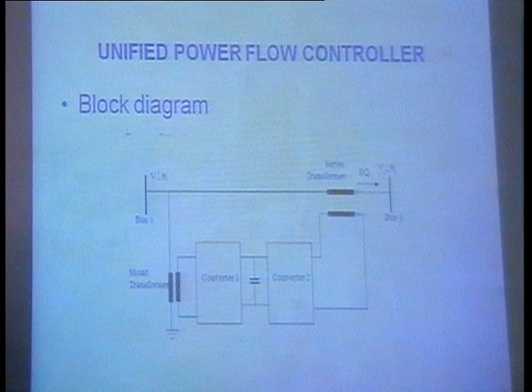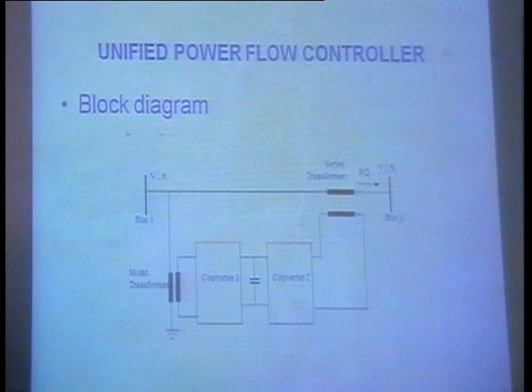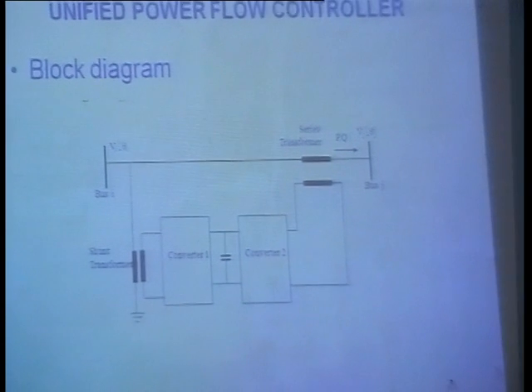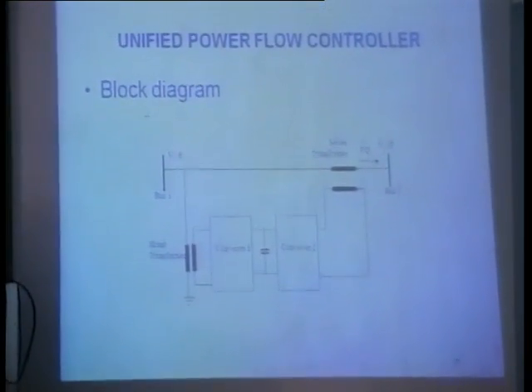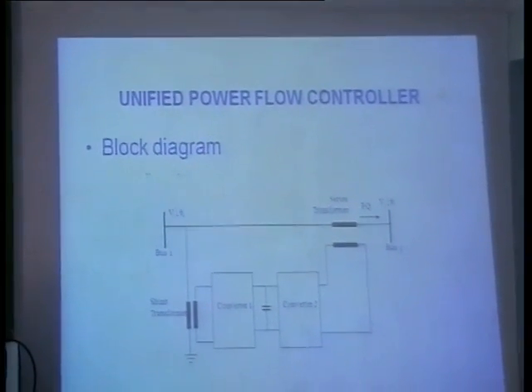Reactive power is sensitive to voltage; real power is sensitive to delta. So to control real power, I play with delta by changing the firing angle of the inverter input — if I change the firing angle of the input, the injected voltage angle will change accordingly.